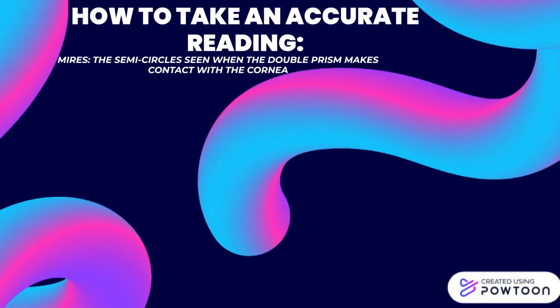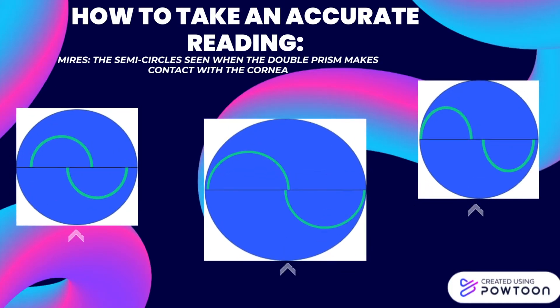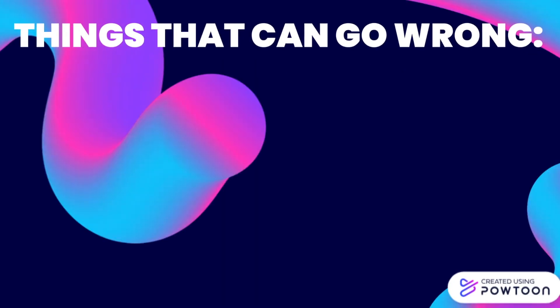When the prism makes contact with the patient's cornea, two semicircles of a green-yellow colour will be seen against a blue background; these are called mires. When taking an intraocular pressure measurement, we want to aim to have the inner margins of both mires only just touching for the most accurate reading, and we use the pressure dial to adjust the positioning. When the mires are too far inside each other, the dial pressure is too high and you need to turn it down. If the mires appear completely separate and away from each other, the dial pressure is too low and needs to be increased. Mires are a different colour because of the uptake of the fluorescein dye, and therefore having too much or not enough dye can be problematic.